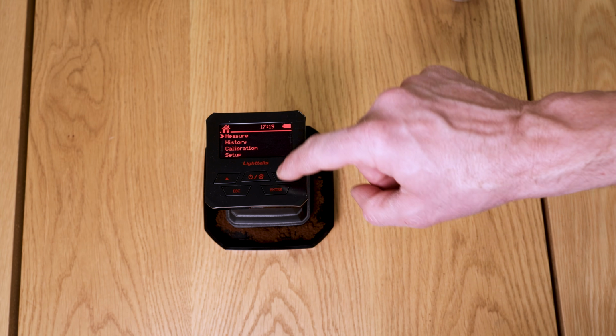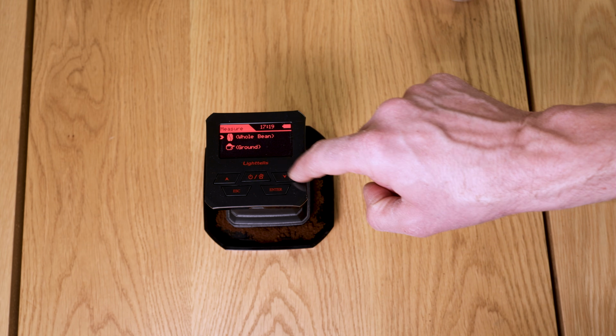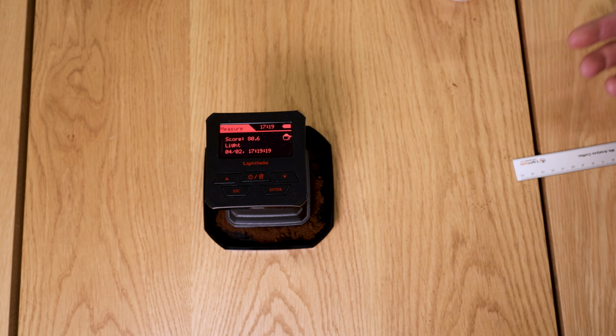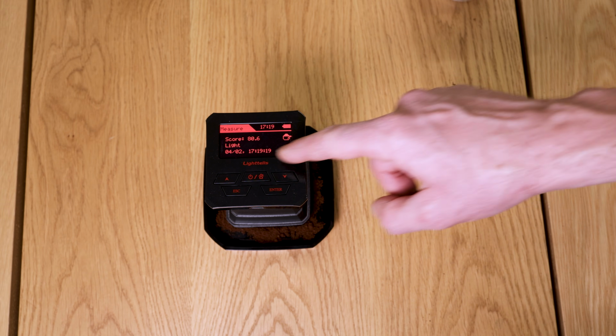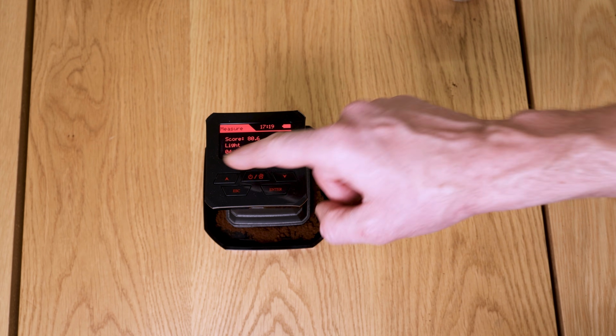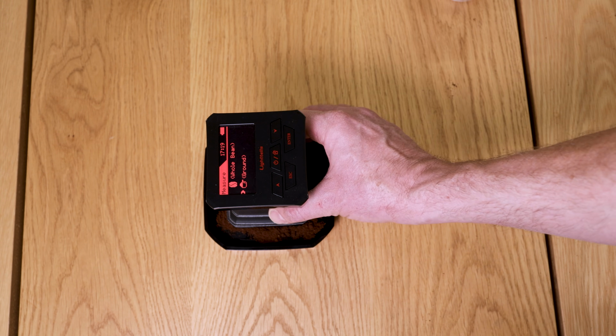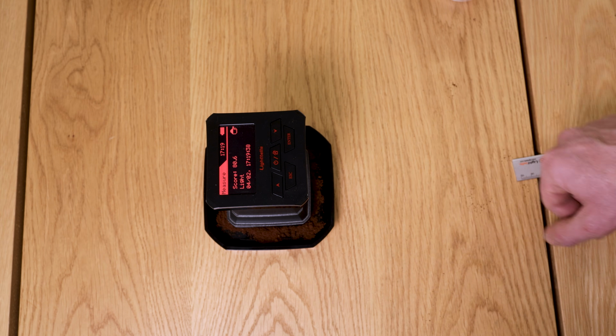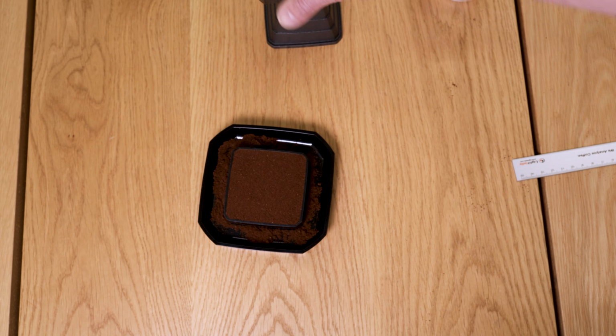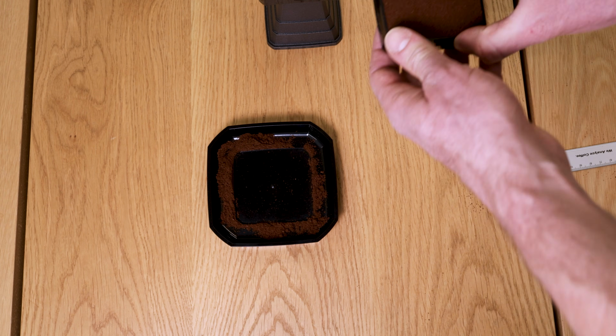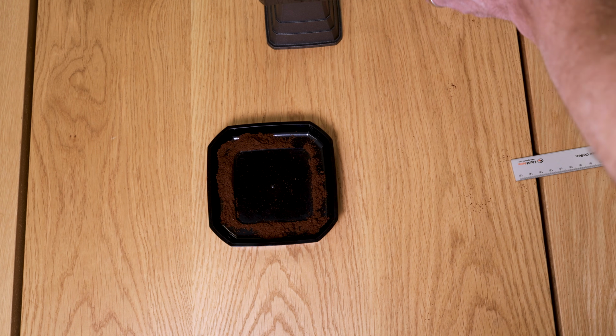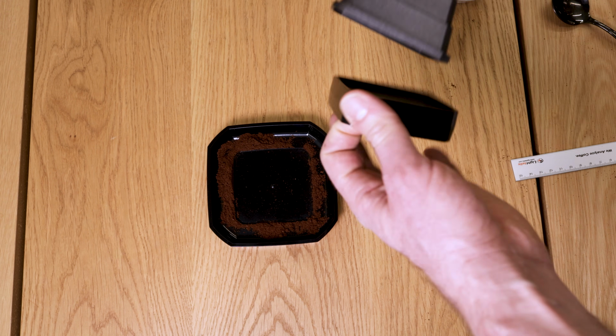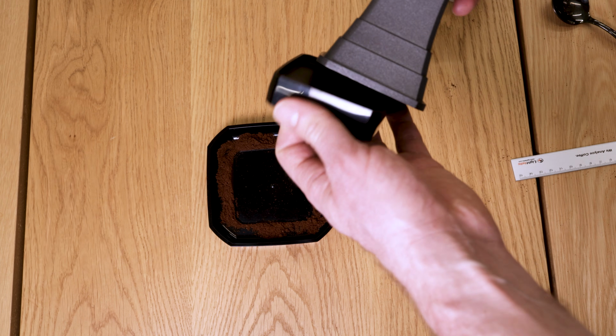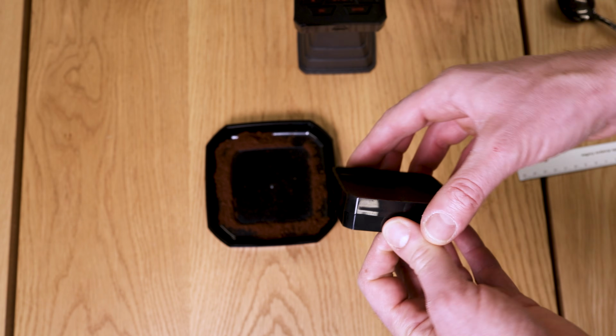And here I have to set, do I have whole beans or ground? I go on ground. It's measuring 80.6 Agtron, so quite similar to what the A1 was measuring. And then here I see this expression light. I go back, can do another one. Ground coffee, 80.6. So you see, usually for ground coffee, the measurements are the same. When I change the device, I just want to make sure that I put it really on the cup and not at any open space. This is why I do more than one reading.